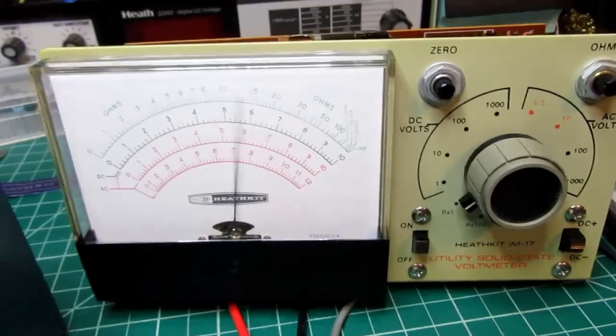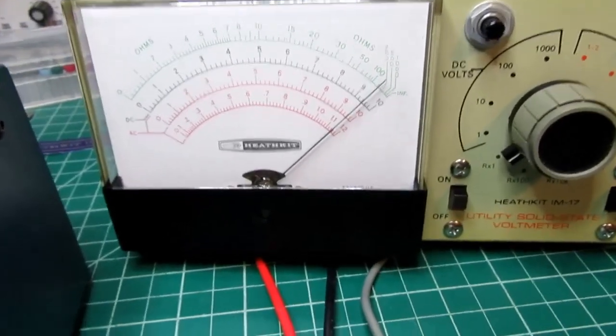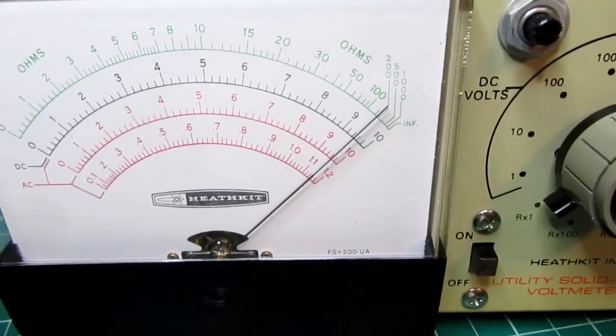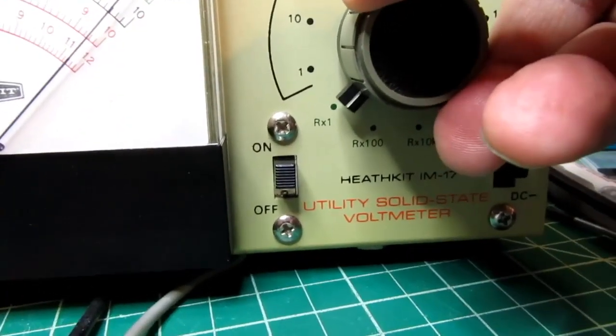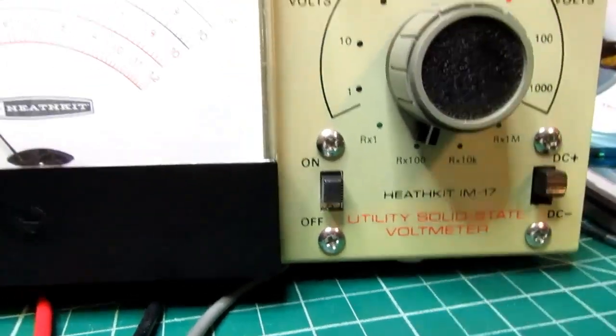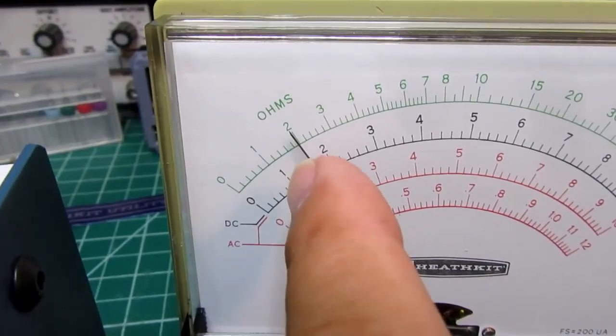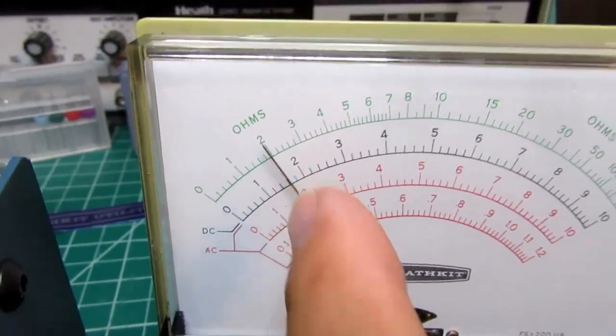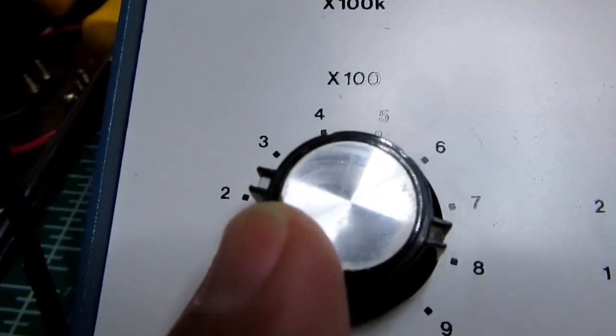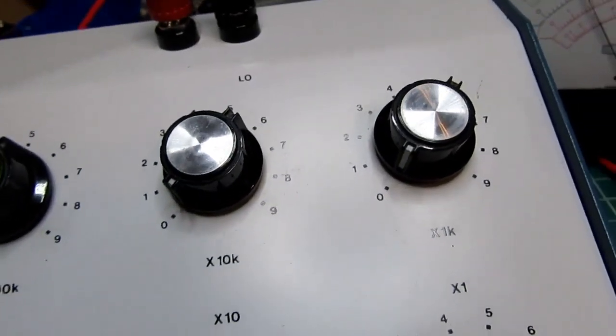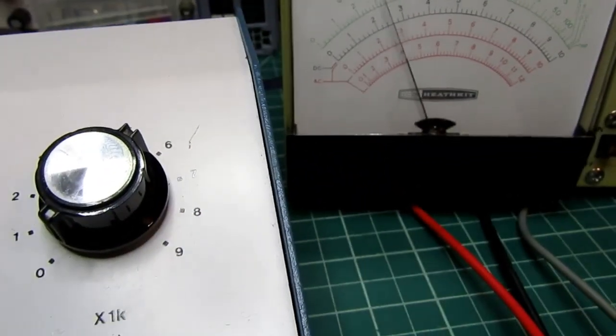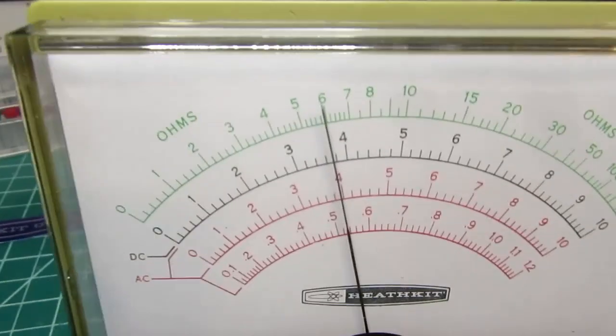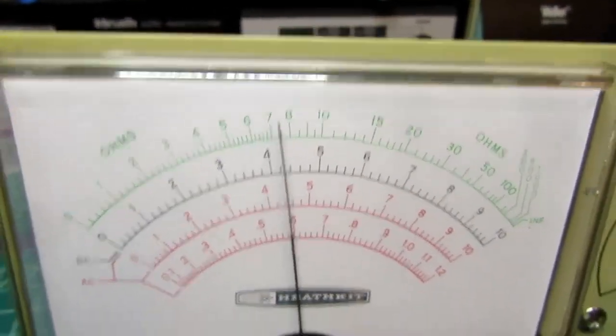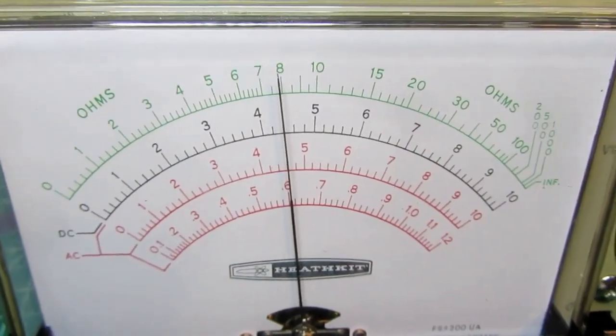So let's go up to 200 ohms, and I'm getting up really high on the meter here, so I'll go to the next scale, which is the times 100 scale. And now I'll take whatever the reading is times 100, so it's right on 2, so that's 200, and that's exactly what I've got here. It's starting to read a little better. Let's go to 600, and it's right on. 800, pretty much right on.